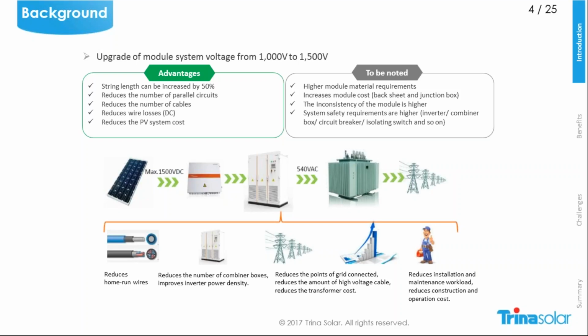Even for Europe, there's a question, why not 1500 volt? Because we have a low voltage directive, and inside the low voltage directive there is a voltage limitation for low voltage of 1500 volt, and the IEC only goes to 1000 volt. Though there was a question in the past why not go to 1500 volt, because it's already allowed in the low voltage directive.